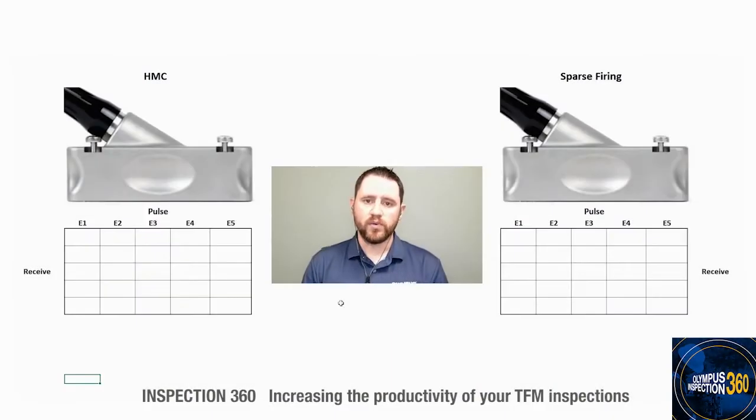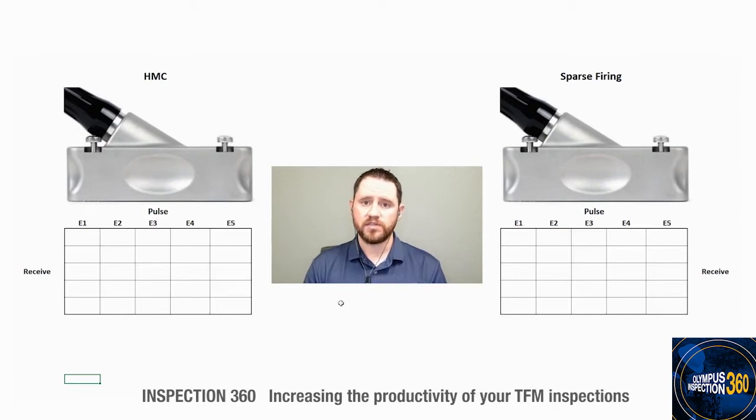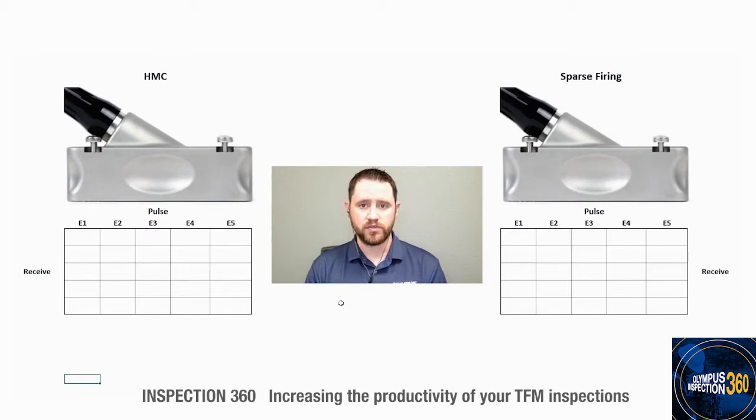Once we get to the end of the presentation, if you have any questions, just type those into the chat and we'll address those straight away. So without further ado, we'll get started with that brief explanation on what exactly the sparse mode is. Let's begin with a brief explanation on how the sparse firing mode works on the OmniScan X3. In a typical TFM inspection, we utilize FMC or full matrix capture as the means of pulsing and receiving signals from a phased array transducer.